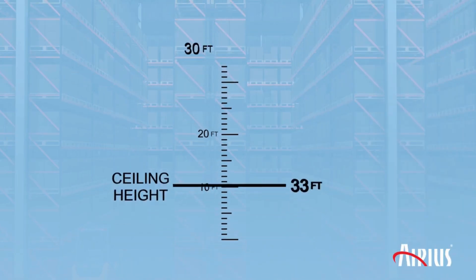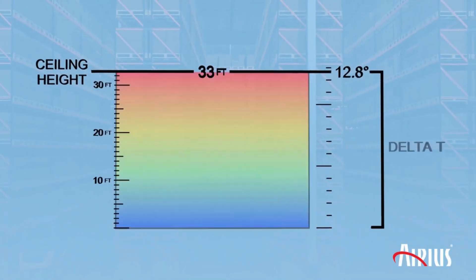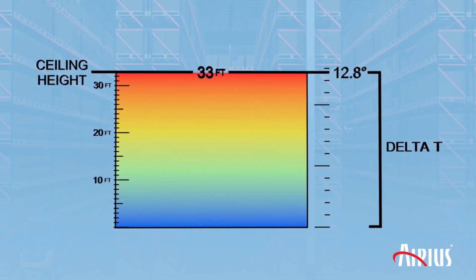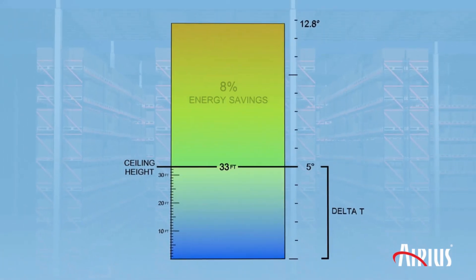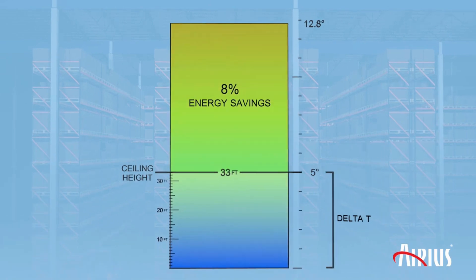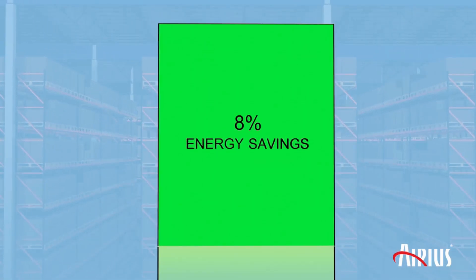This savings chart is from BSRIA, a UK-based non-profit that looked at the cost of stratification with a computational fluid dynamic model. If your building has a 33-foot-tall ceiling with a delta T of 12.8 degrees and you can reduce it to 5 degrees, you've saved about 8% of the energy bill and tens of thousands of tons of carbon.